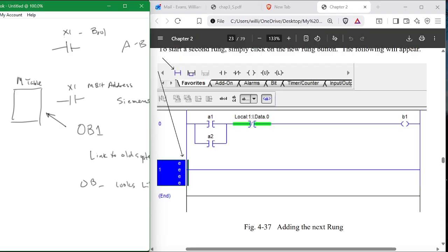You'll see, with Allen Bradley, online, if you make a mistake, you'll see green, and then you'll see a bunch of E's and gray. And if you see that on your online program in Allen Bradley, it means that you've not verified this area and this part of it is not running. It's running up here where there's green, but right here, this part of it is not running. Okay? And you have to go back and verify it and test it.